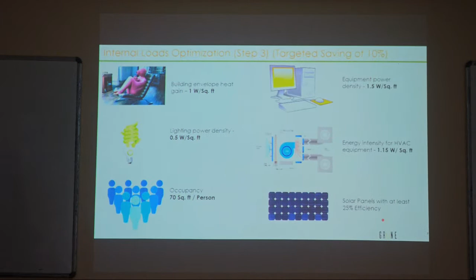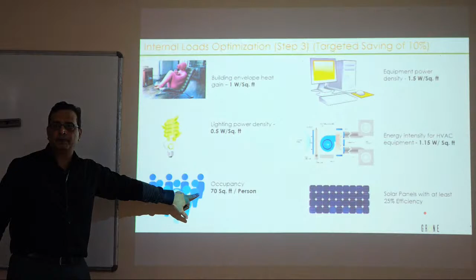Definition of occupancy per square foot depends on the setting. In an auditorium, we generally consider 10 square feet per person. But if this opens up to an office, it becomes almost 70 square feet per person. Banqueting halls for hotels or auditoriums use occupancy of 10, but if I design an office for 10 square feet too, it's way beyond actual consumption. If you stuff people in, like in BPOs, you get 25 to 40 square feet per person—that's just cramming people in. So defining occupancy correctly in a building is critical.